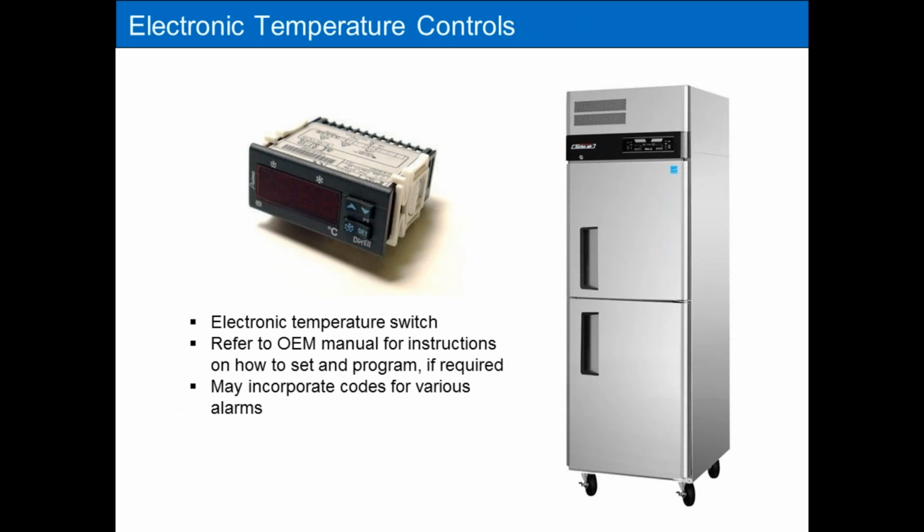You'll come across some of these reach-in coolers that have digital temperature sensors, and the rules don't change because it's digital versus mechanical. So it's the same approach, it's just a different style of temperature sensor, but troubleshooting it is the same manner.